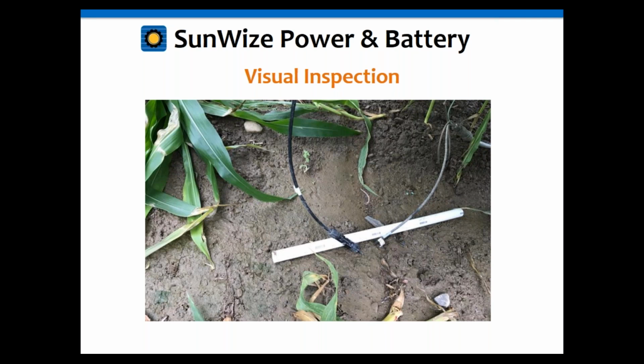Again, if this would have been caught in maintenance, if somebody would have noticed that the wire was chafed, it could have been repaired either with some heat shrink or electrical tape or something else, or even replaced before the system failed. But what had happened was it wasn't, and therefore the copper wire under the insulation that got exposed corroded, and corroded enough that it actually caused the wire to break and separate, disconnecting the solar module from the system and thereby causing the system to fail. So again, this is why it's so important to do these inspections to prevent things like this from happening. And when they do happen, you can find them easily as well just by doing the visual inspection and maintenance.